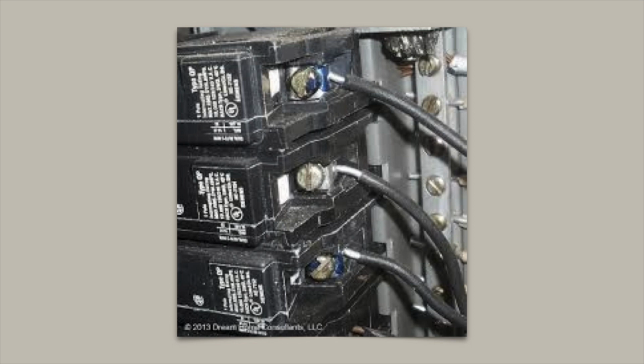Aluminum wiring was used in residential housing from the mid-1960s to the mid-1970s because of a copper shortage caused by the demand needed to supply the Vietnam War effort. Aluminum is a softer material than copper, which was used for connections and screws in the box and/or in outlets around the house. Aluminum and copper have different thermal expansion properties, therefore aluminum expands and contracts at a different rate when current is running through the wires. The connections become loose, causing micro-arcing and the breaker to fail. This is a safety hazard.